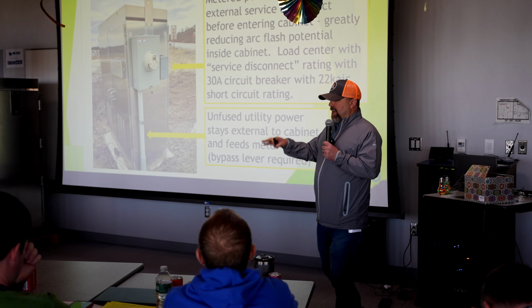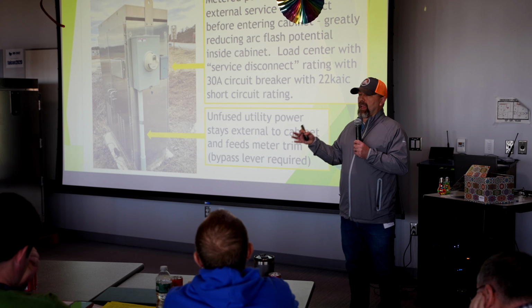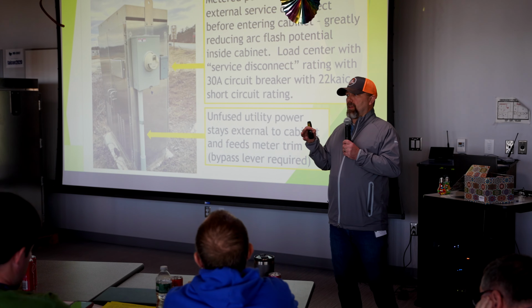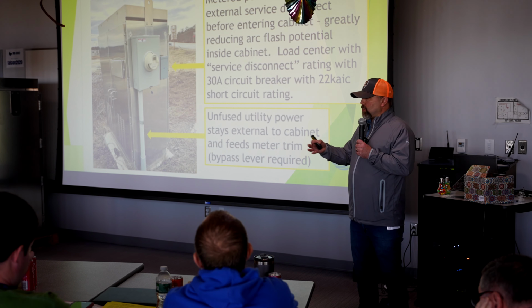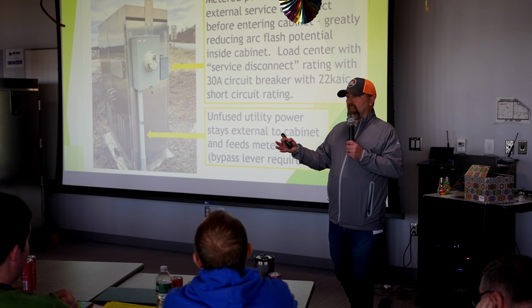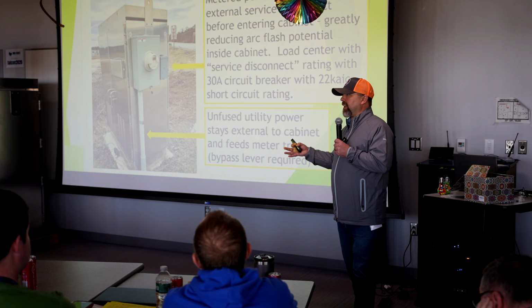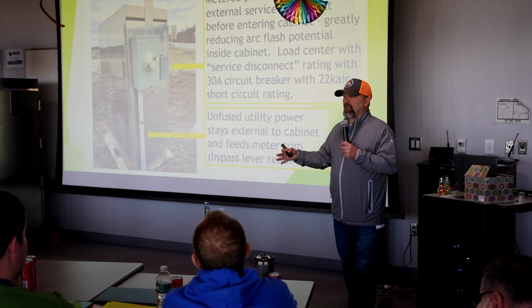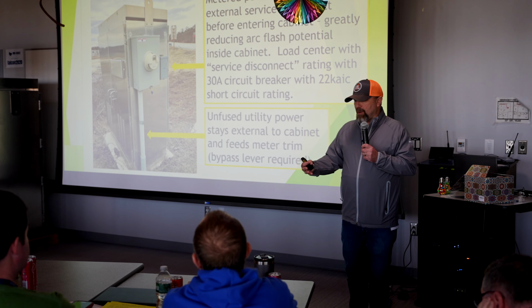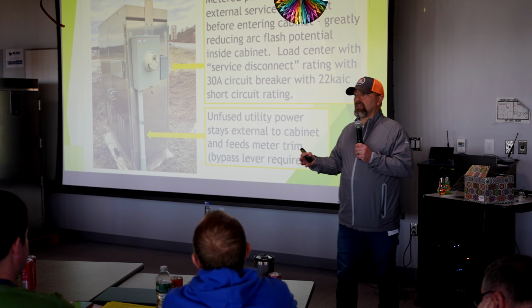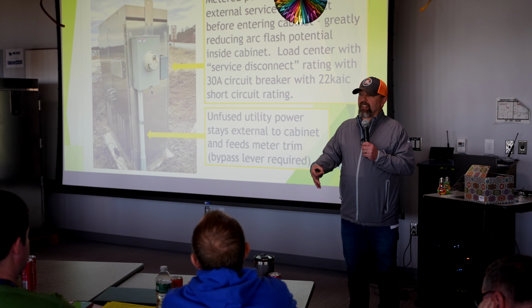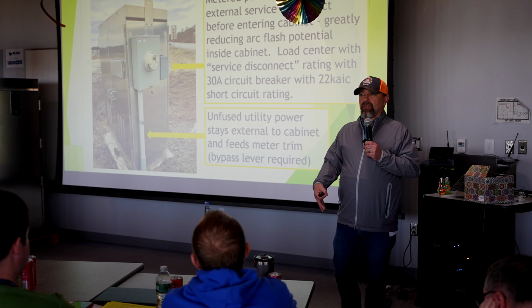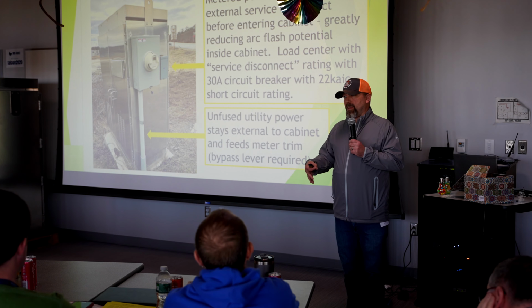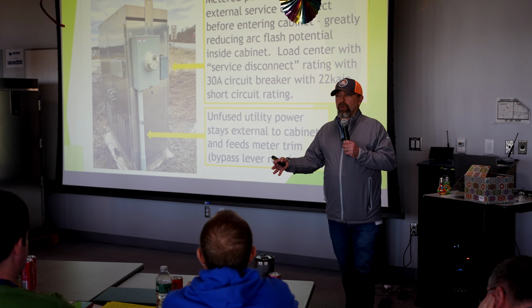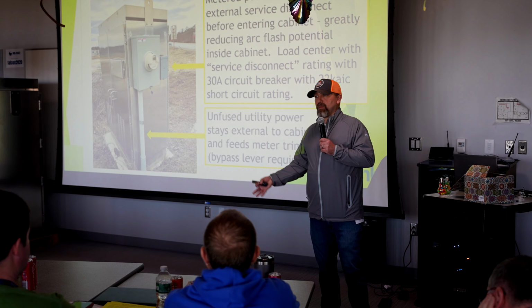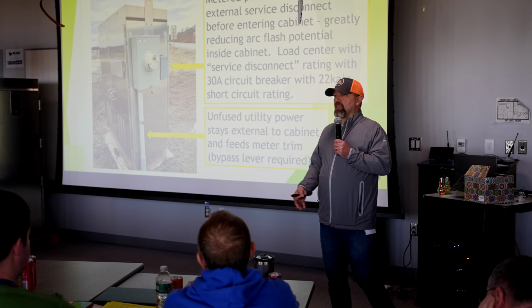When I was on the contractor side trying to do this, it became very cumbersome, because the PVC conduit, I think most people would agree, is going to stand up over time. But the concrete encased protection was a major hurdle, because on the project I was on, where we were doing a hundred of these, that concrete needed to be tested and QC'd like it was a mast arm foundation. It basically became unaffordable, because you're not going to get a concrete truck to show up to pour a quarter of a yard just for your electrical service.